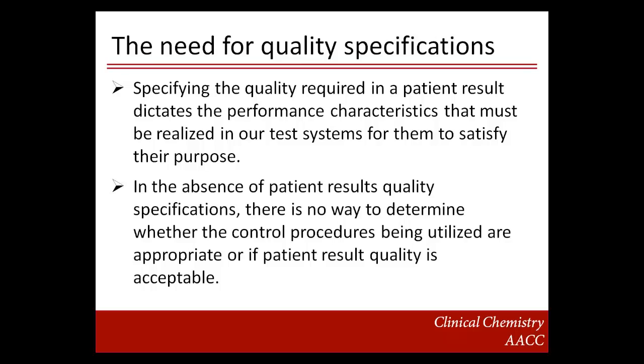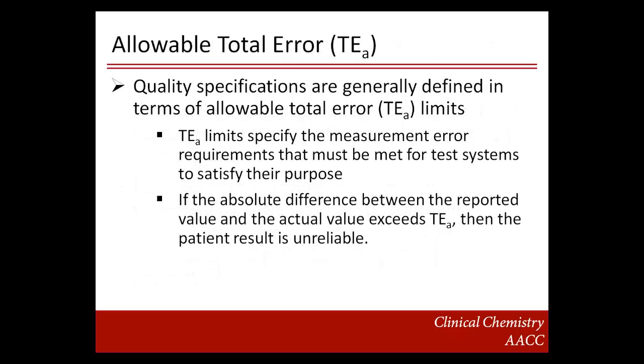The quality specifications dictate the performance characteristics of our test system so we know when the test system fails. In the absence of quality specifications, there is no way for us to determine if the control procedures being utilized are appropriate or if the quality of the patient result is acceptable. Quality specifications are generally defined in terms of allowable total error limits, TEa.